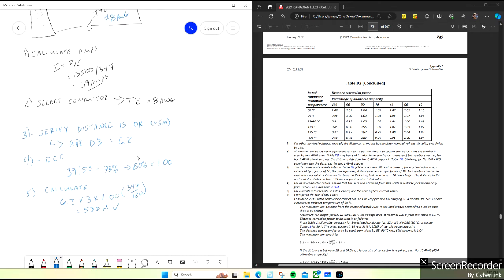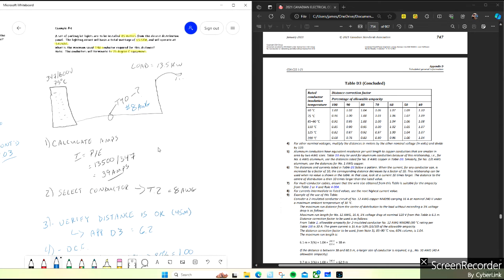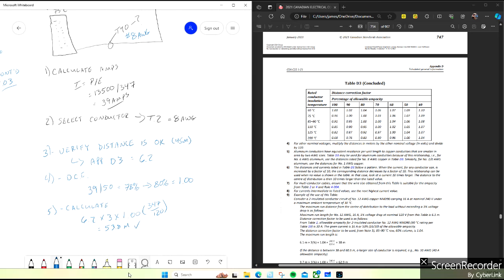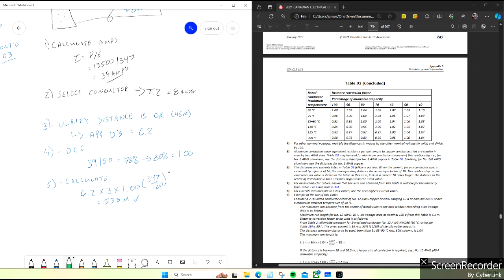But say this was 65 meters or 60 meters even, whatever. Maybe 70 meters. Then if it was 70 meters, this would not be good enough. Number 8s would not be large enough, right? We wouldn't have enough, there would be too much resistance in the wire, right? So what do you do now? Well, easy. I'm just going to switch pens. Let's pretend that the installation is 70 meters.